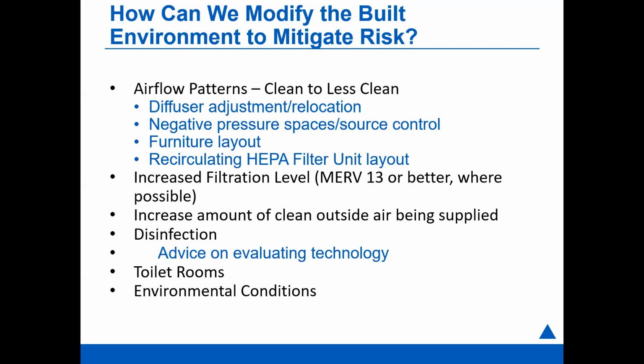Once you get about 2 air changes per hour of outside air in a space, that's kind of a minimum. If you were down at like an 8 or 6 in filtration, I'd look to increase the filtration level to get up to a MERV 13 minimum. Once you hit that MERV 13 minimum, I'd go back and look at increasing the overall air change rate and outside air percentage to a space, just as general guidance. But again, every situation is unique, so you really want to have your situation evaluated.